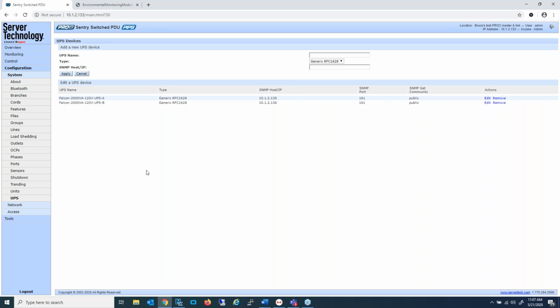Now, what I have logged into is a PRO2 master PDU linked to a link PDU. So one master and one link PDU, 2 separate circuits, and they are both plugged into 2 separate UPSs. That is to have true redundancy and no single point of failure. I've already defined the two UPSs, but it was as simple as starting by a name of your choosing. I chose for my first UPS, Falcon 2000 volt amp, 120 volt UPS A. I used the drop down over here and selected my brand of UPS, which is a Falcon brand, Falcon Engineering. If you do not find your brand of UPS in this list, please try the generic RFC 1628 option. Nearly all UPS systems support that RFC, even if they have their own support. So for example, Liebert, I know, supports both their own MIB and generic. If you don't find yours in the list, choose generic.